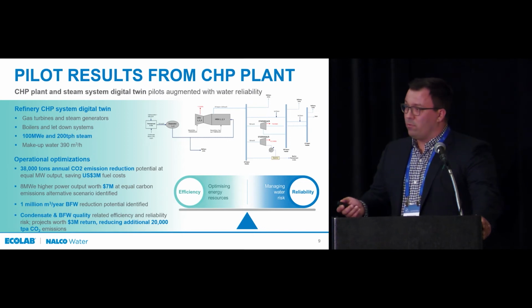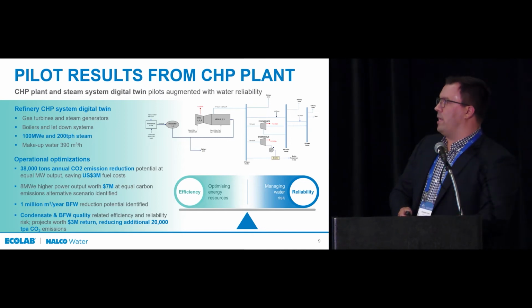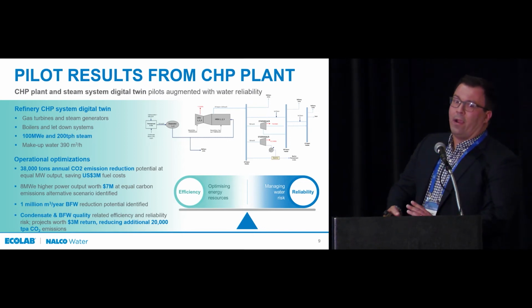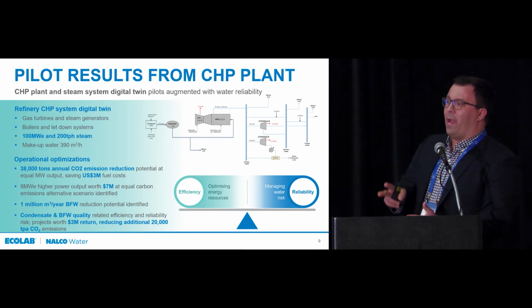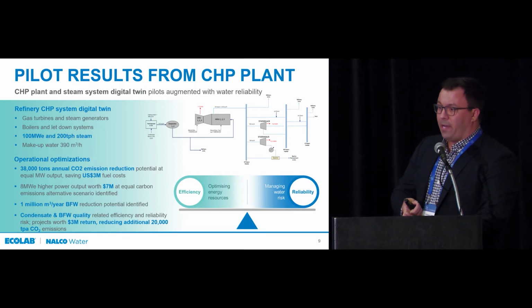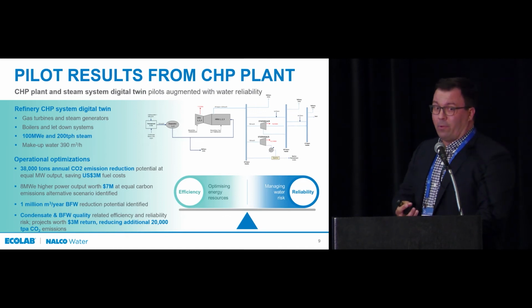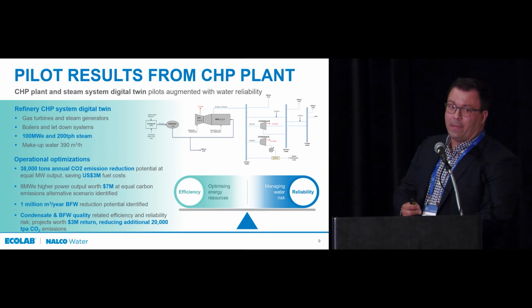What we found running this study was that this plant had two areas of low-hanging fruit. Their condensate return was nowhere near optimized, they were only returning about half of what they could have, which brought down consumable costs. Secondly, their boiler feed water quality was not being maintained where it needed to be.